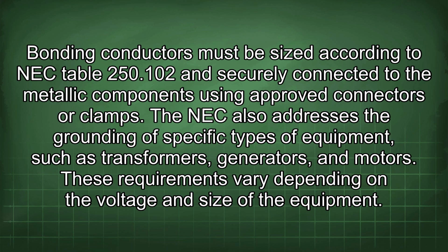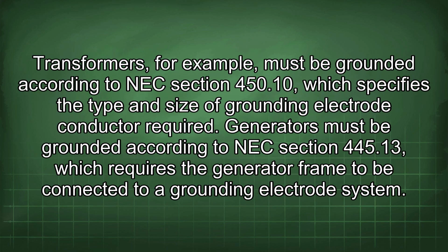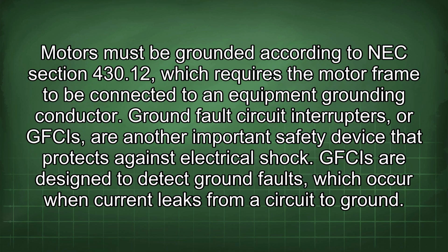The NEC also addresses the grounding of specific types of equipment, such as transformers, generators, and motors. These requirements vary depending on the voltage and size of the equipment. Transformers, for example, must be grounded according to NEC Section 450.10, which specifies the type and size of grounding electrode conductor required. Generators must be grounded according to NEC Section 445.13, which requires the generator frame to be connected to a grounding electrode system.